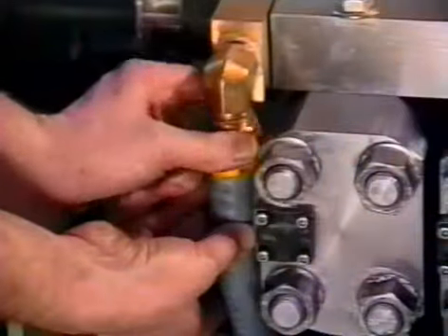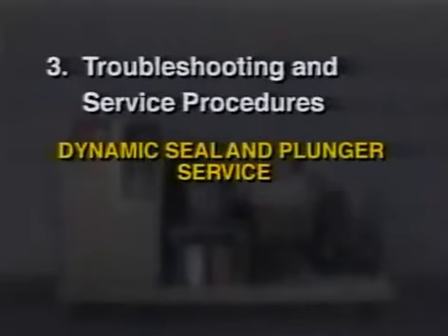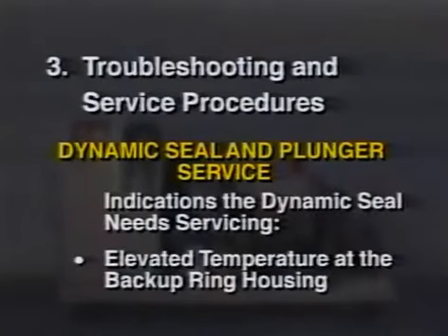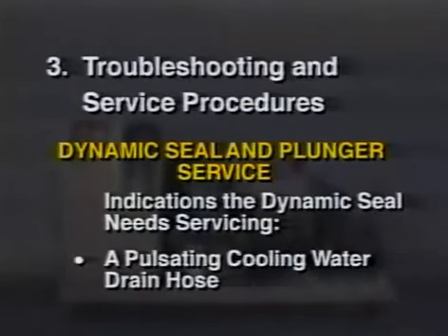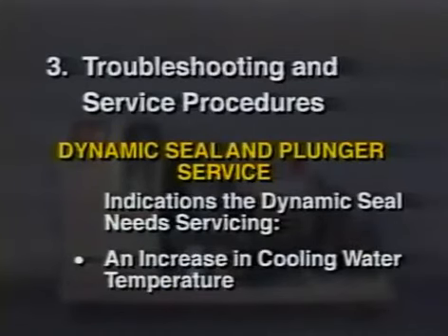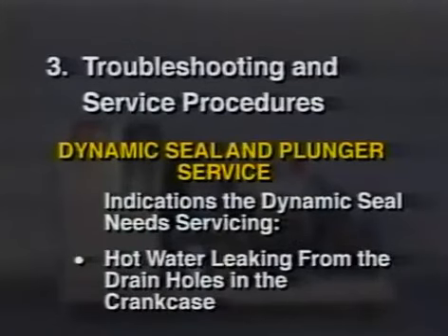Dynamic seal and plunger service. There are several indications that the dynamic seal needs servicing. Elevated temperature at the backup ring housing. A pulsating cooling water drain hose. An increase in cooling water temperature. Hot water leaking from the drain holes in the crankcase.